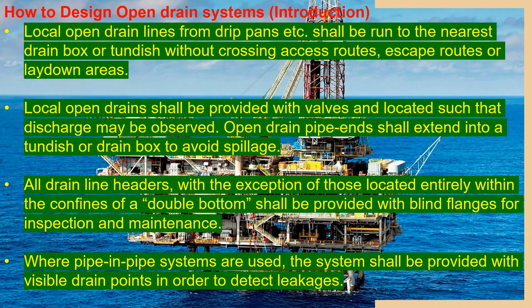Local open drain lines from drip pans, etc., shall be run to the nearest drain box or tundish without crossing access, escape routes, or lay-down areas. Local open drains shall be provided with valves and located such that the discharge will be observed.